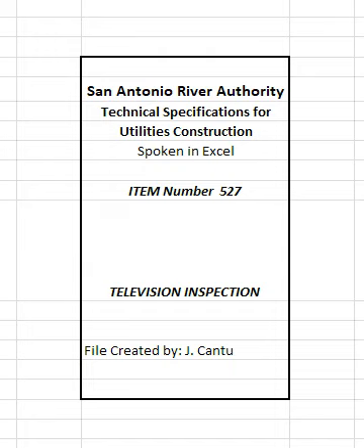If repairs are required, they must be made and the repaired section subsequently television inspected to ensure correction of the deficiencies. The cost of all repairs shall be the responsibility of the contractor. Sewer lines shall be cleaned from manhole to manhole immediately prior to television inspection. Contractor shall add water to new pipes so sags and bellies can be located.